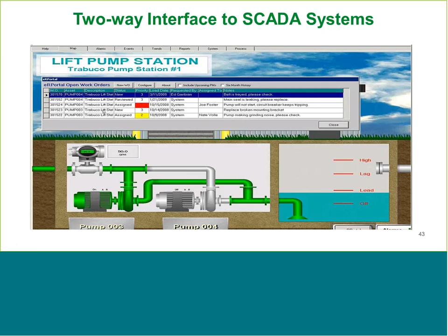We can drive maintenance work orders based on real-time conditions coming from SCADA. For example, I can set a set point so that if temperature, vibration, or pH goes above a level for a certain duration and triggers a high alarm state, it automatically generates a maintenance work order request, getting a document out to the field so people can check what's going on.